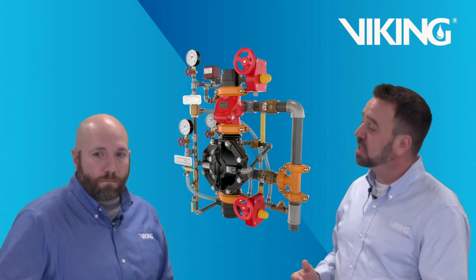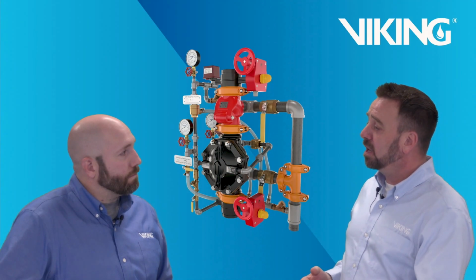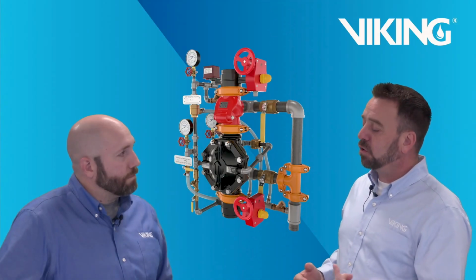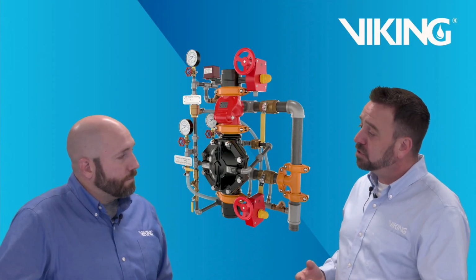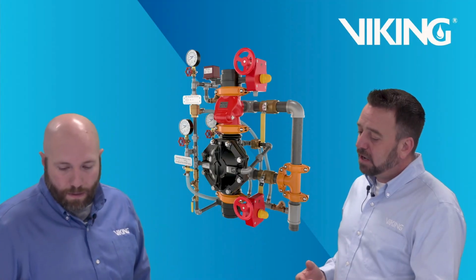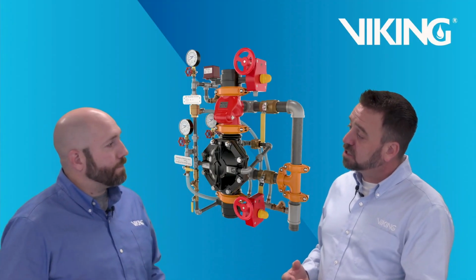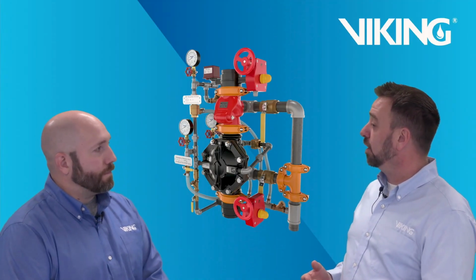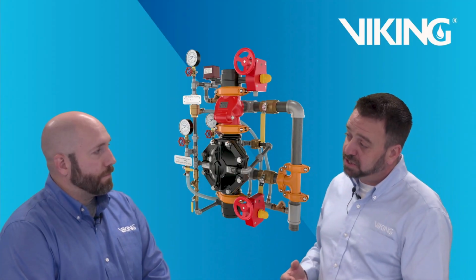So it has the exact same takeout. It'll have a solenoid for single interlock or your double interlock electric electric, or it will have a solenoid and a pneumatic actuator if you're upgrading to a double interlock electric pneumatic pre-action system.